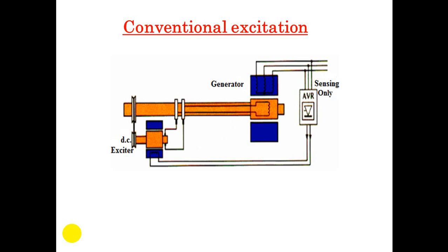What is the generator excitation system? Excitation system is an important part of AC synchronous generators, which controls the voltage and reactive power of the synchronous generator. In addition, the speed control system controls the speed or frequency and active power of the prime mover and the generators. What are the main control systems for the generator set or genset? The excitation control system is a feedback control system composed of a synchronous generator and its excitation system.